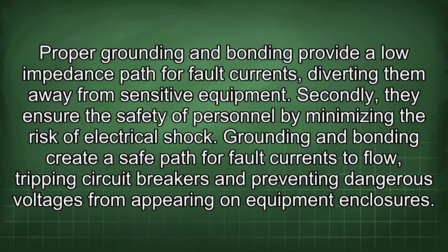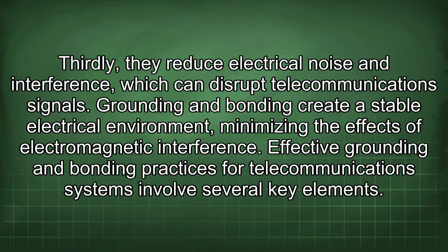Grounding and bonding create a safe path for fault currents to flow, tripping circuit breakers and preventing dangerous voltages from appearing on equipment enclosures. Thirdly, they reduce electrical noise and interference, which can disrupt telecommunications signals. Grounding and bonding create a stable electrical environment, minimizing the effects of electromagnetic interference.